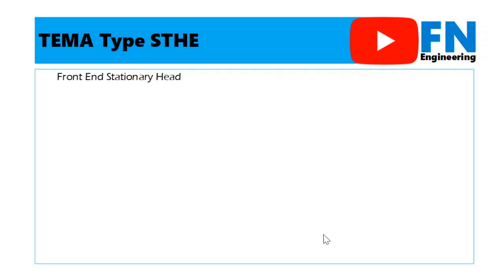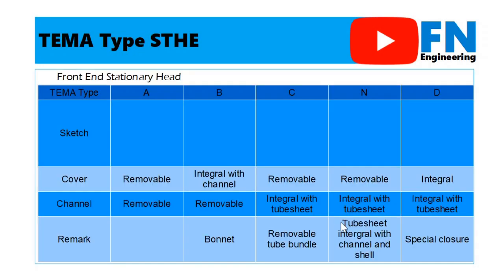Alright, in the next material, we are going to know shell and tube heat exchanger configuration based on the TEMA standard in more detail. First, we are going to explain the front end stationary head. There are 5 types of configuration: type A, type B, type C, type N, and type D. The characteristic of each type can be distinguished in the part of the cover or channel.